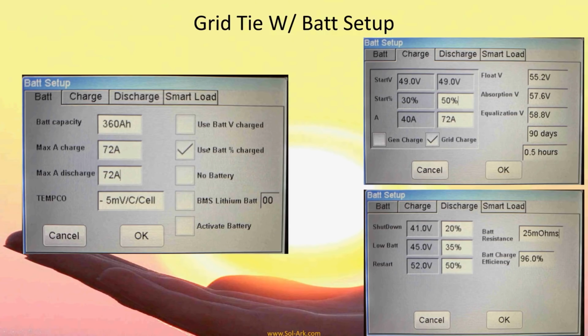So the basic things, besides what we just talked about for grid setup and setting up the time, is we want to set the battery capacity and we want to set the max charge and discharge amps. So I typically do about 20% of the battery capacity. I like battery percent charge more than voltage because customers understand it better. I'll click OK, and then I'll go back in here and look under the charge tab. This max charge amps here is how much the PV array will charge the batteries. This is the master charge value, so it doesn't overly charge your batteries too fast.